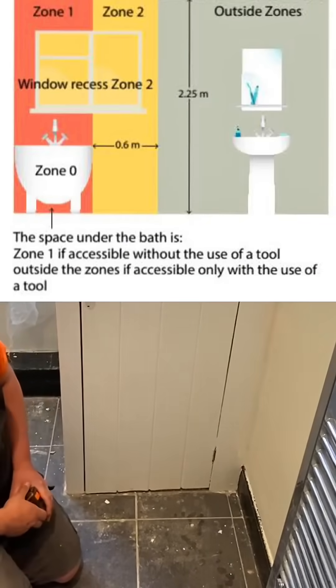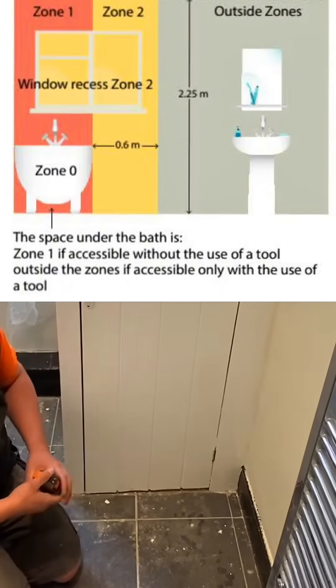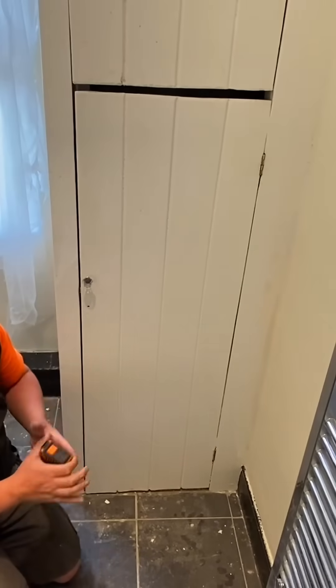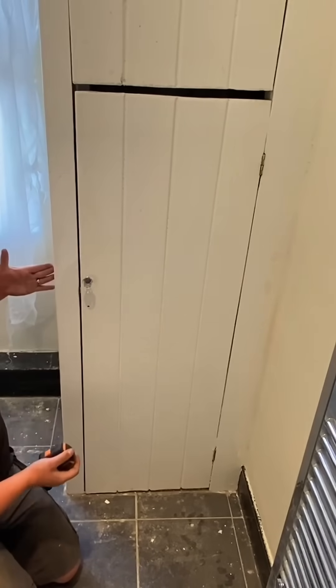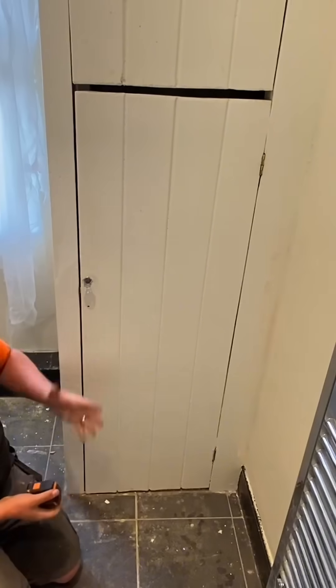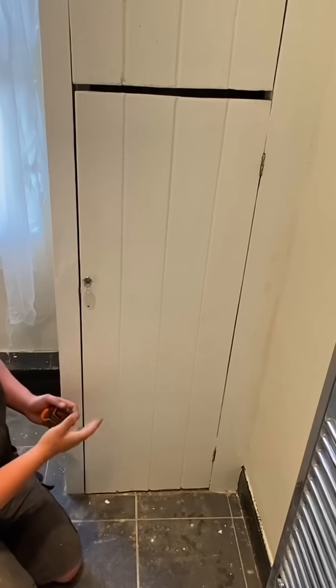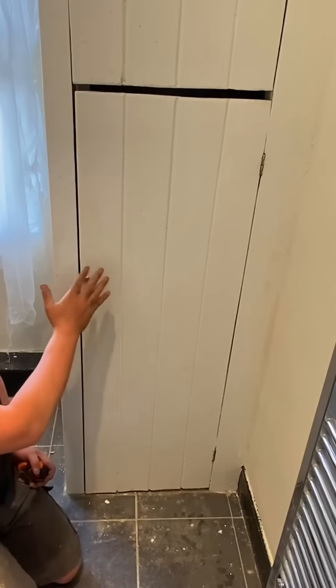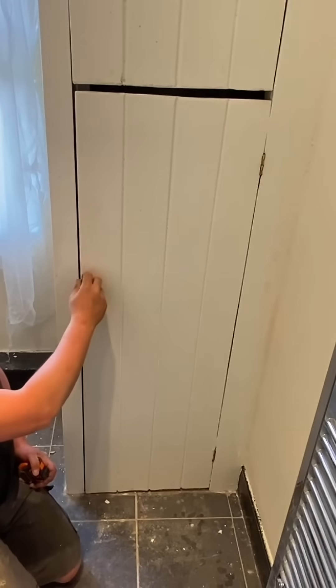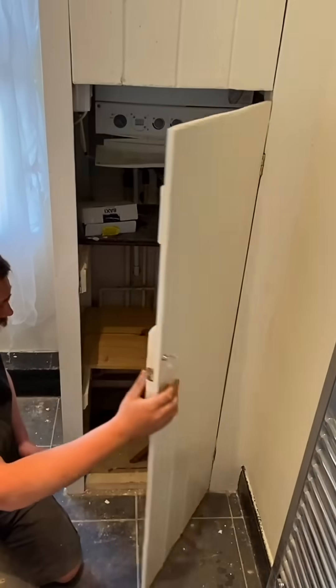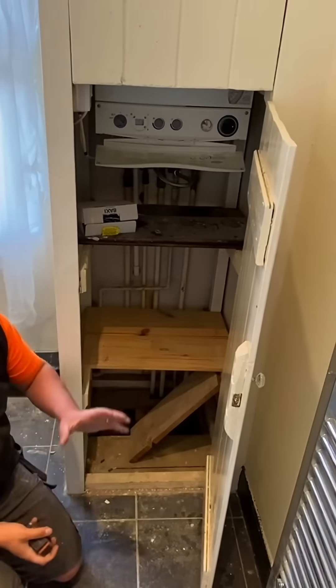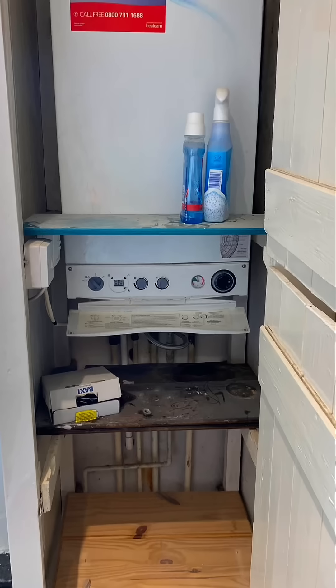Would zone two actually go part way into the airing cupboard? No, it wouldn't. The same way you move into a different location when you walk through the bathroom door — the same principle applies here. Because we have a door on the airing cupboard, the space inside is actually classed as not being in the special location itself. When the door is open, we could be in zone two.